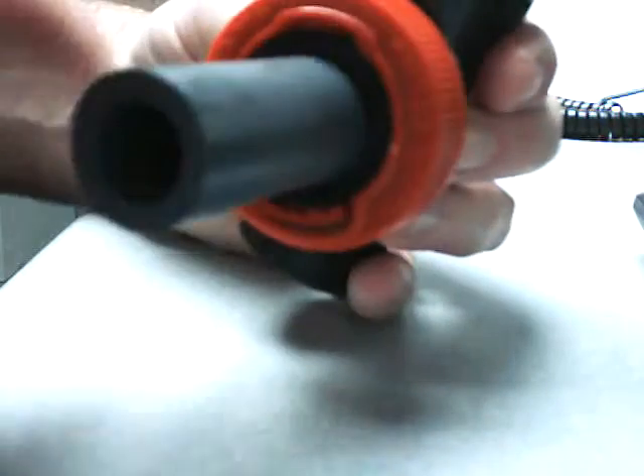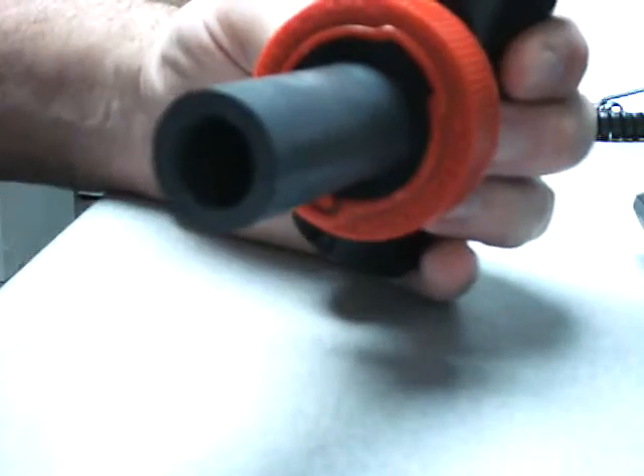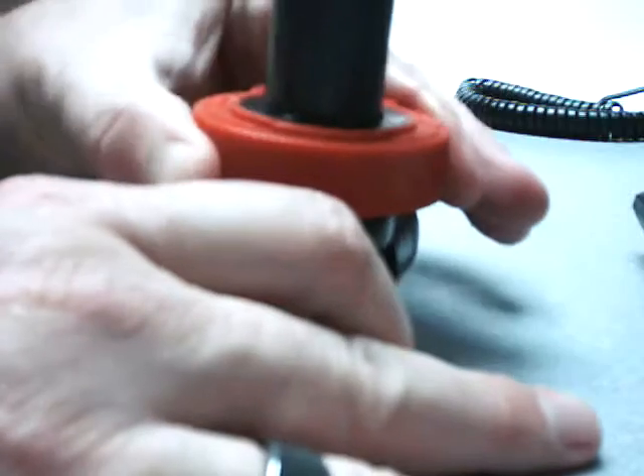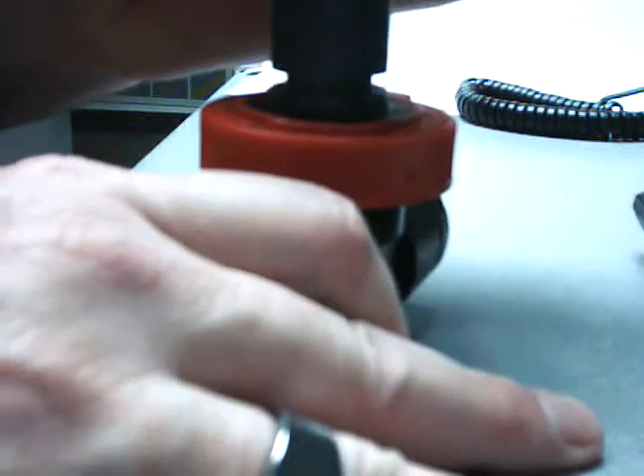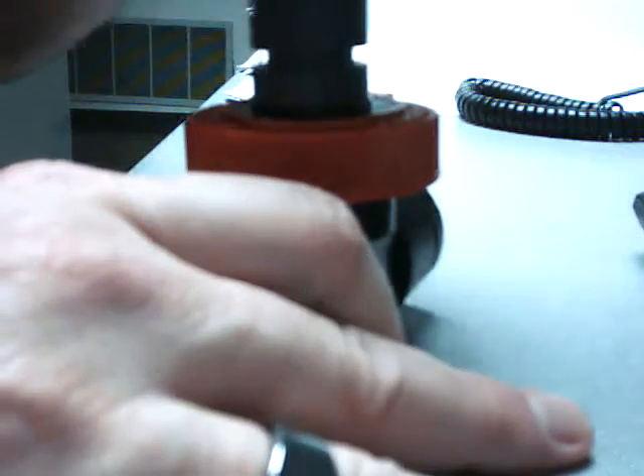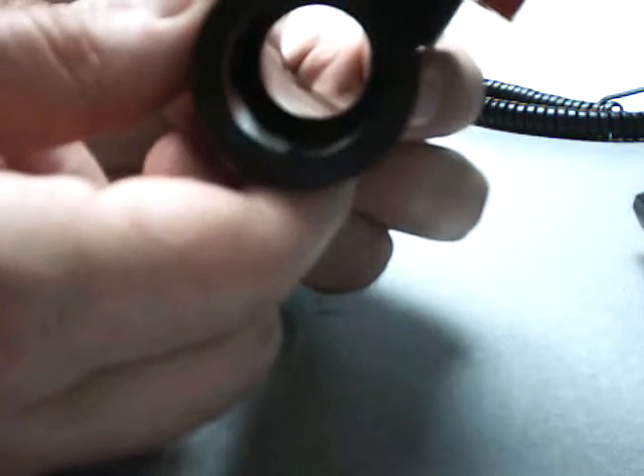The cool part about that is at time of cleaning, the person in the field basically undoes the lock ring and very quickly withdraws the probe, can clean it, reinsert it, and lock it up again. And by using this twisting motion, he can withdraw the sensor easily and put it back in. And internally, I'm shining into that diameter for constant measurement.